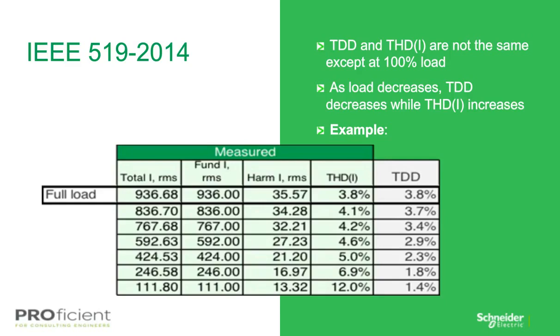So in conclusion, what we see is that if your electrical system can handle the harmonic current at FLA, then it can handle the harmonic current at any other load point because it is less than full load.